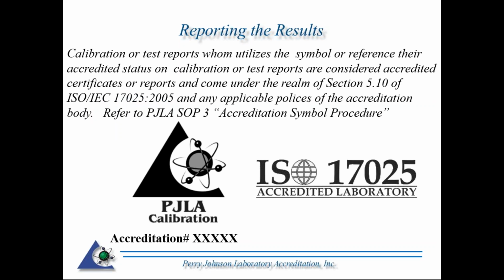So once again, reporting the results. A lab that utilizes a symbol or references their accreditation status on calibration or test reports, those are considered accredited certificates or reports and come under the realm of section 5.10 of 17025 and any applicable policies of the accreditation body.